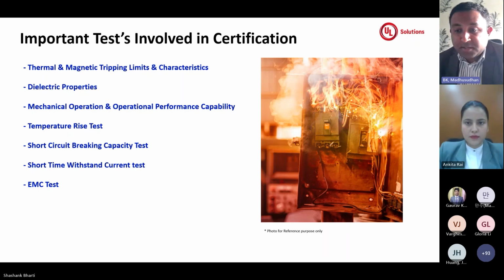And during the temperature rise test, if the declaration from the customer is that the products are enclosed or unenclosed: if it is unenclosed type, the breaker will be tested in an open area. Whereas if the customer declares that it is an enclosed type, then the breaker will be tested within an enclosure. So these differences are critical during this test. Based on the declaration, testing will be conducted.